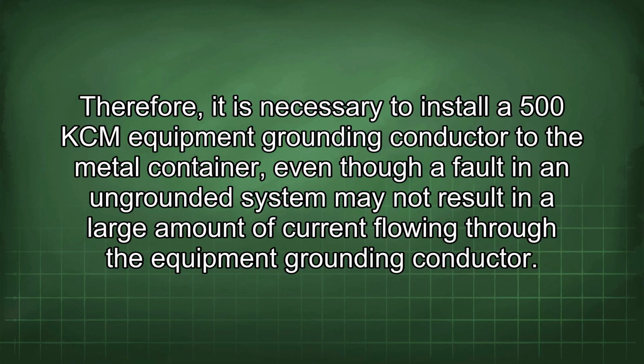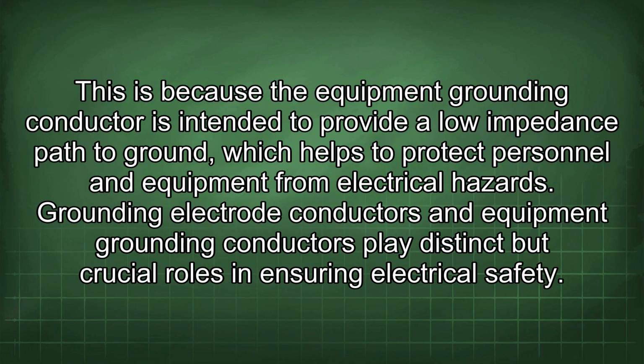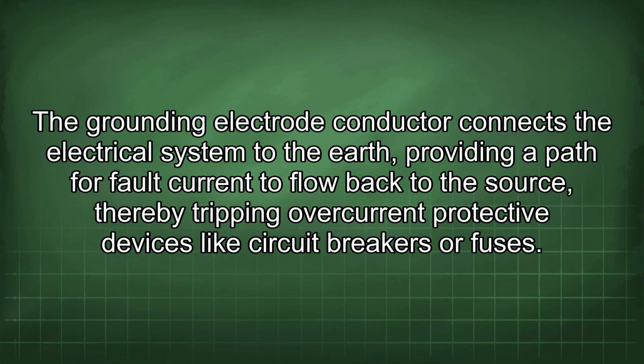though a fault in an ungrounded system may not result in a large amount of current flowing through the equipment grounding conductor. This is because the equipment grounding conductor is intended to provide a low impedance path to ground, which helps to protect personnel and equipment from electrical hazards. Grounding electrode conductors and equipment grounding conductors play distinct but crucial roles in ensuring electrical safety. The grounding electrode conductor connects the electrical system to the earth, providing a path for fault current to flow back to the source, thereby tripping overcurrent protective devices like circuit breakers or fuses.